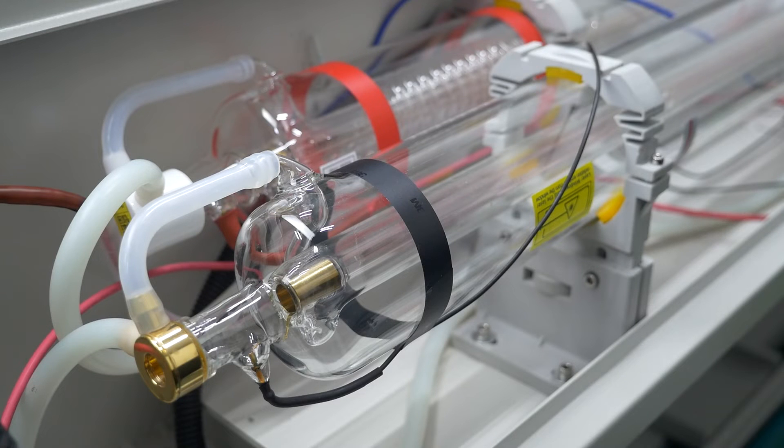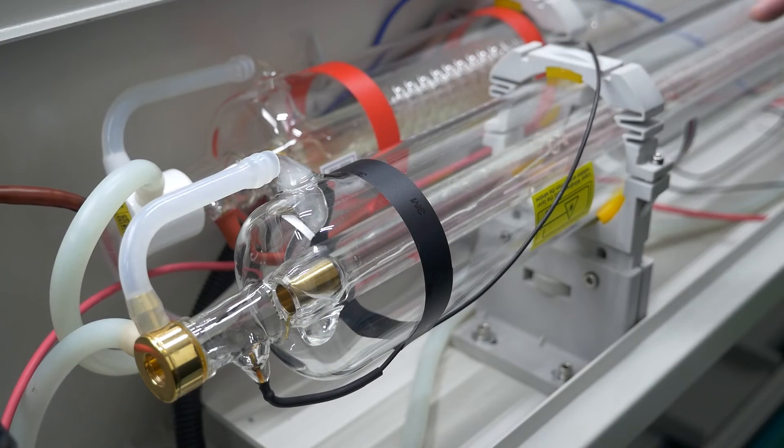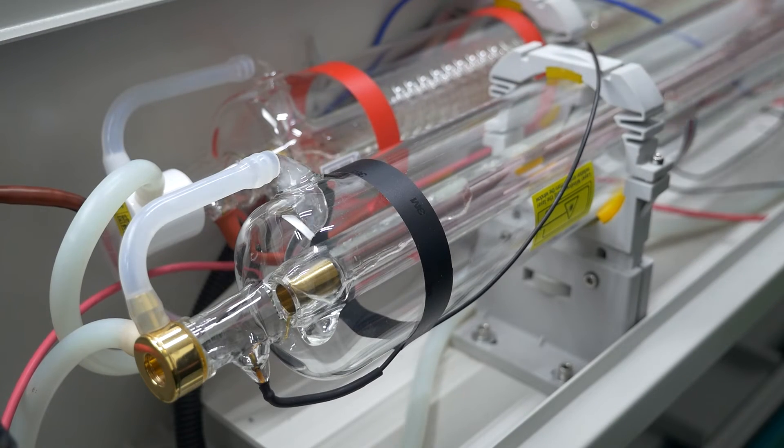Start the chiller. Make sure that the water is supplied to the laser tube in the direction of the laser beam exit. Look closely at the air bubbles inside the laser tube cooling circuit.